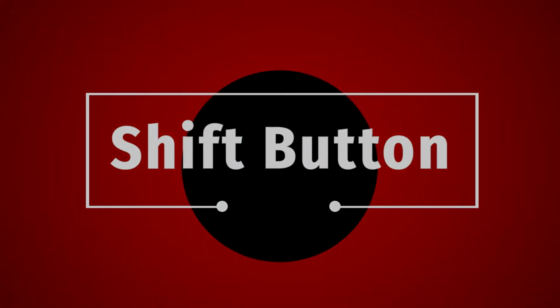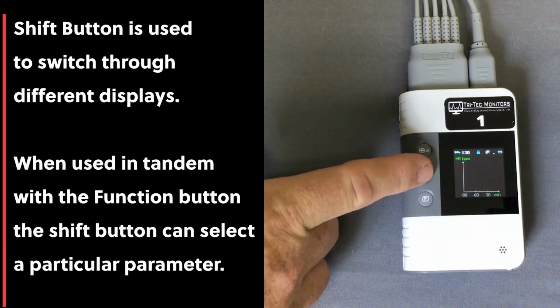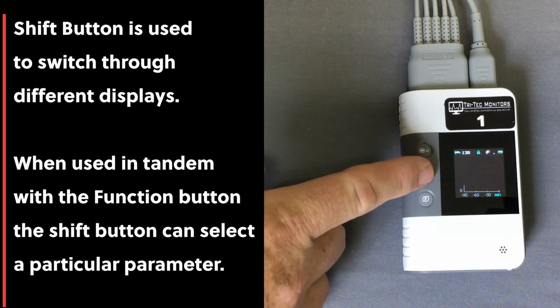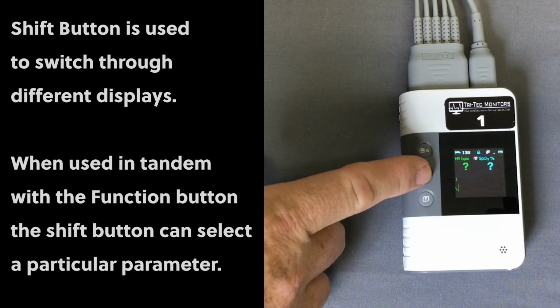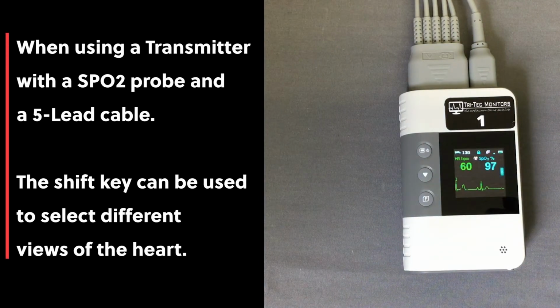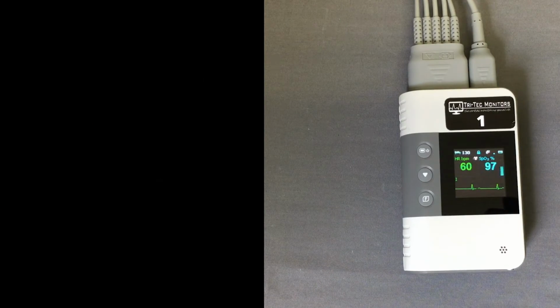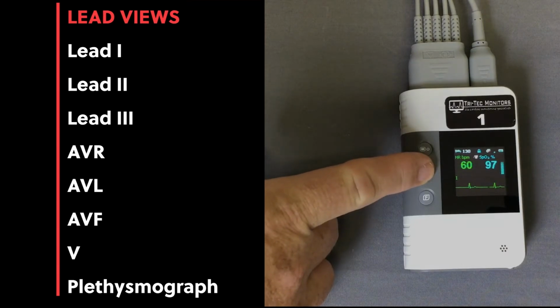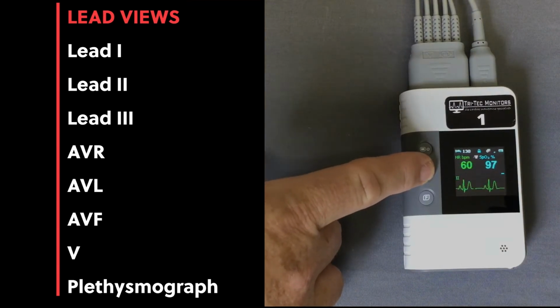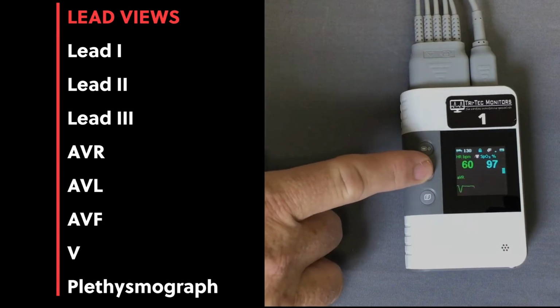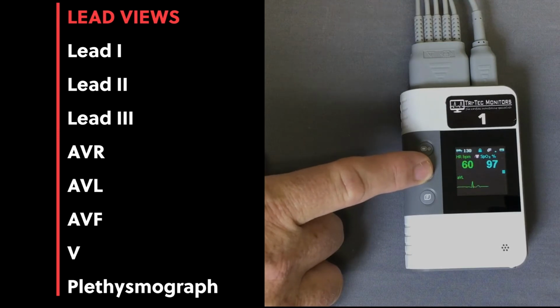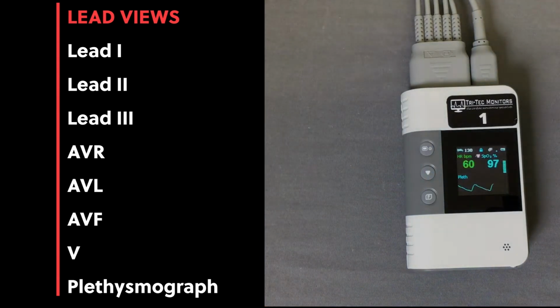The shift button. The shift button is used to switch from screen to screen. When used in tandem with the function button, the shift button is used to select and show a particular parameter. For example, when using a transmitter equipped with a 5-lead cable and SpO2 probe on a patient, the shift key can be used to select the different waveform views of the heart that you can monitor right from the transmitter's display. Starting with lead 1, then lead 2, then lead 3, then AVR, augmented vector right, then AVL, augmented vector left, then AVF, augmented vector foot, then lead V, and finally the SpO2, plethysmograph waveform.